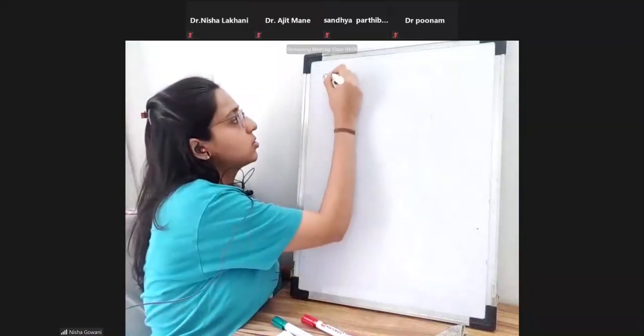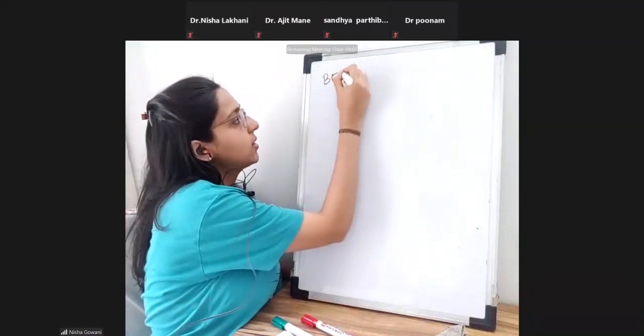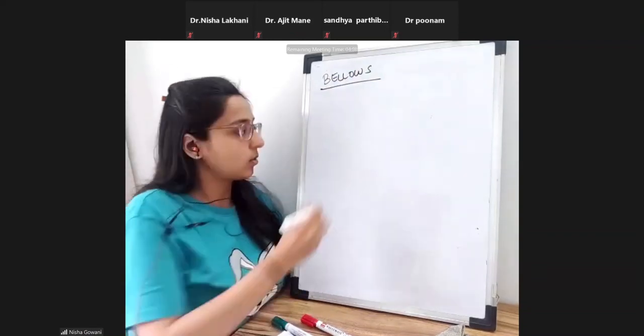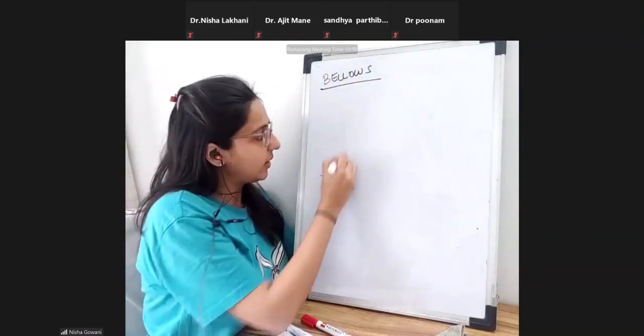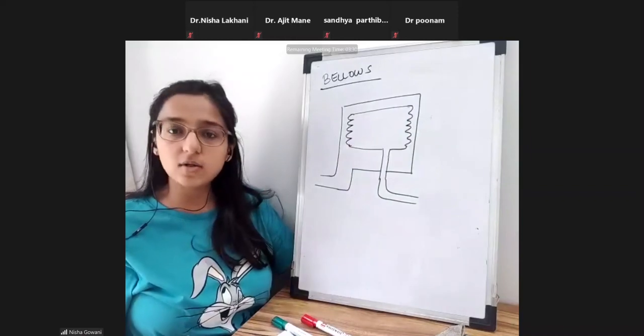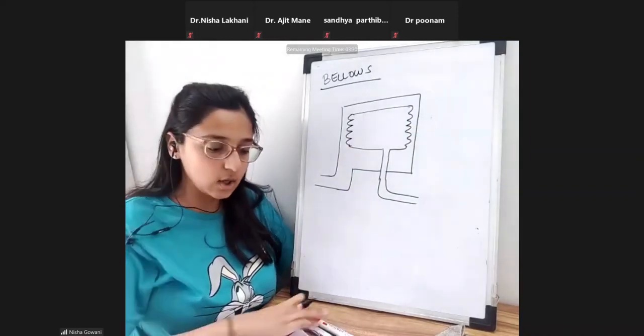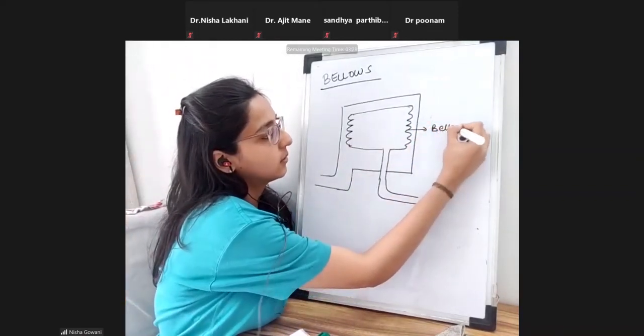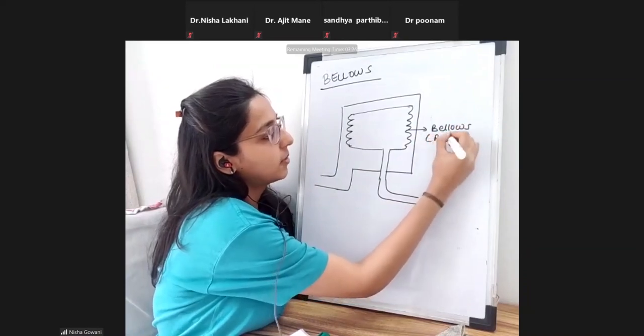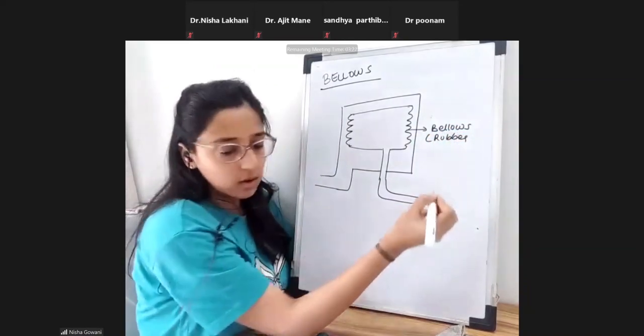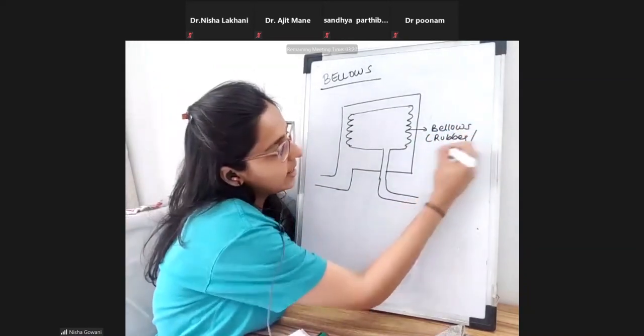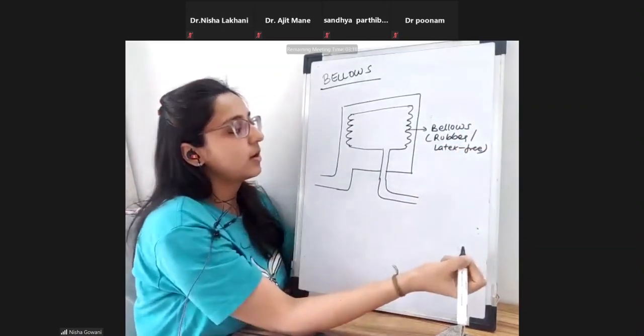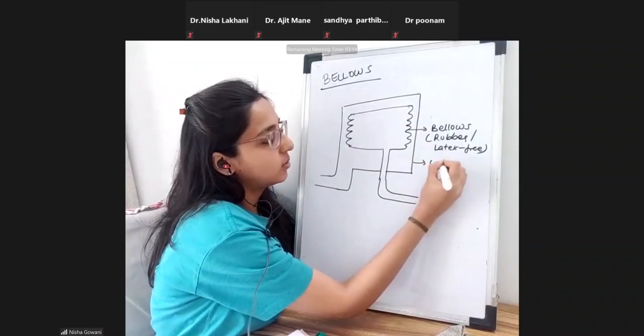As I told you, there are two types of ventilator: one is the bellows and one is the piston type of ventilator. So how does the bellows ventilator look? This is how a bellows ventilator looks. This is the bellows — it is made up of rubber or any latex-free material; it has to be latex free. This is the housing of the bellows.